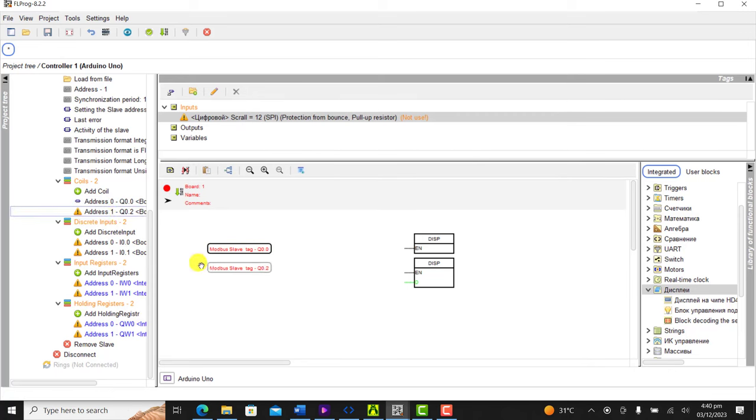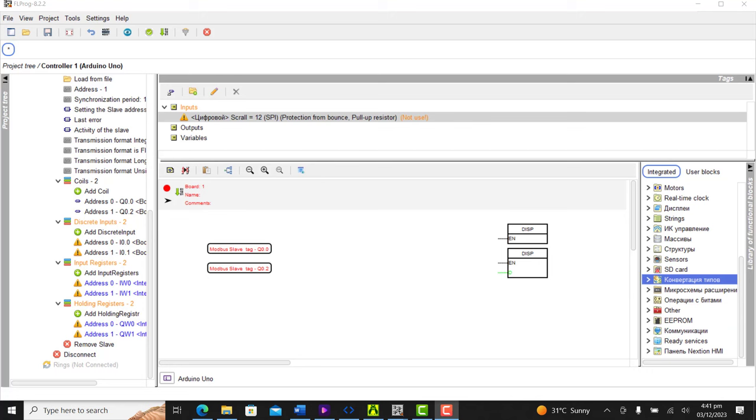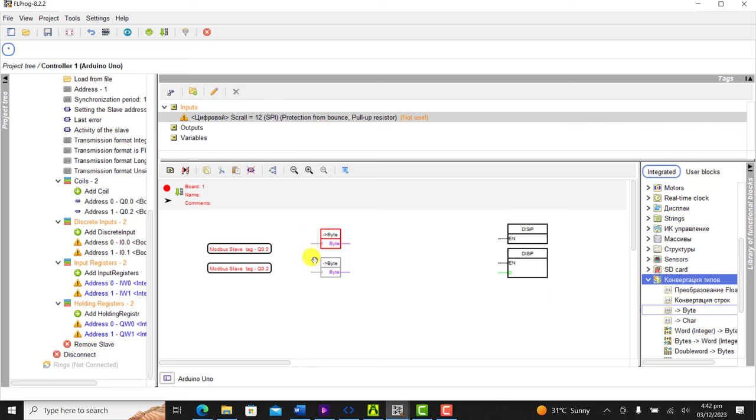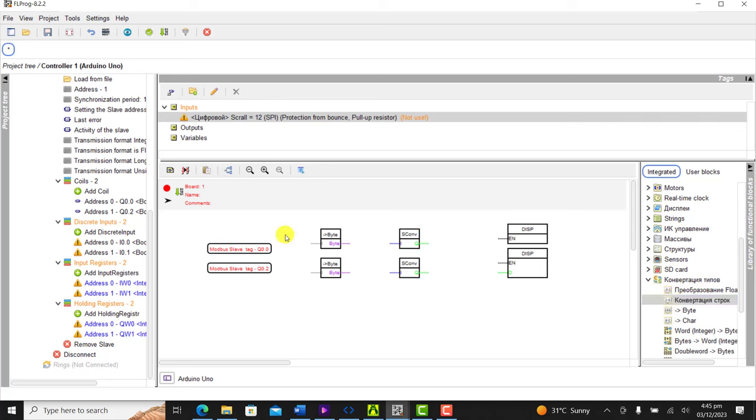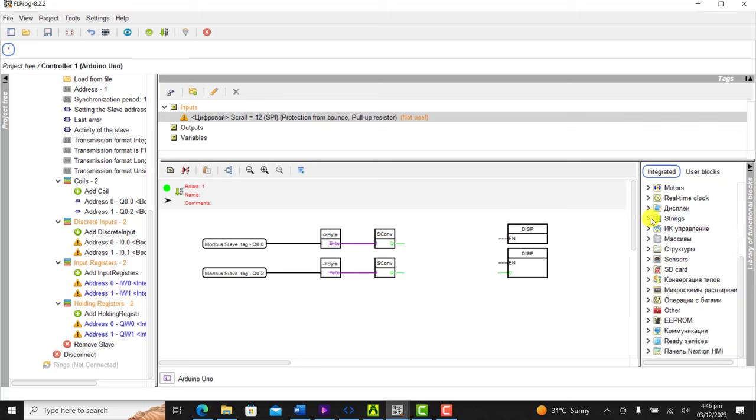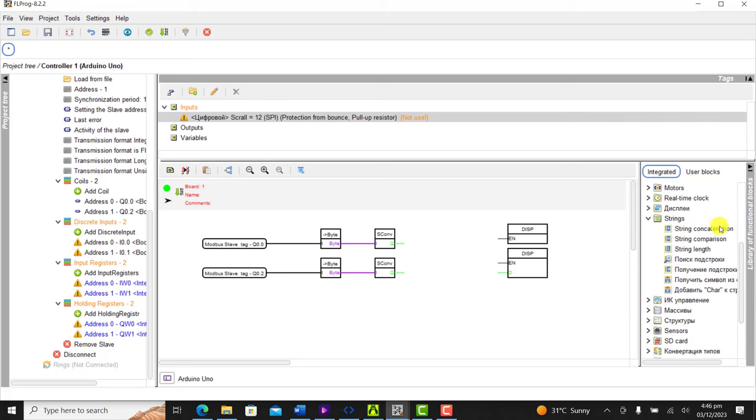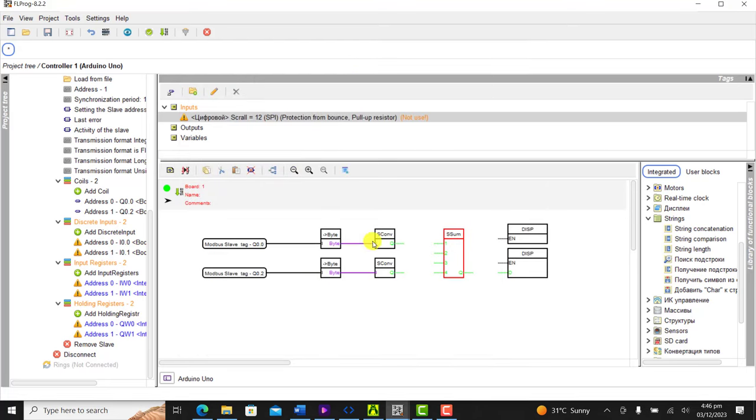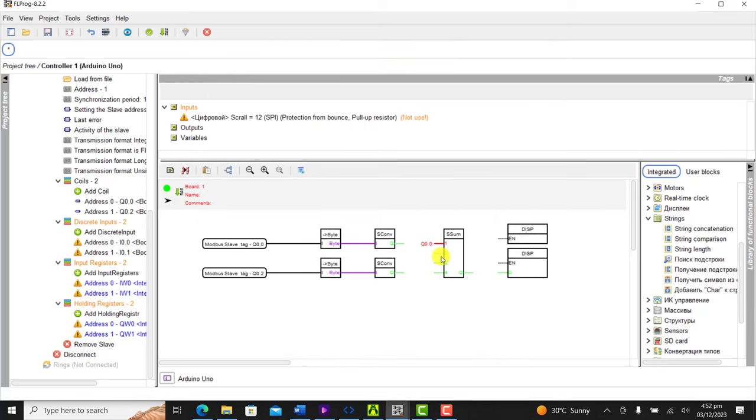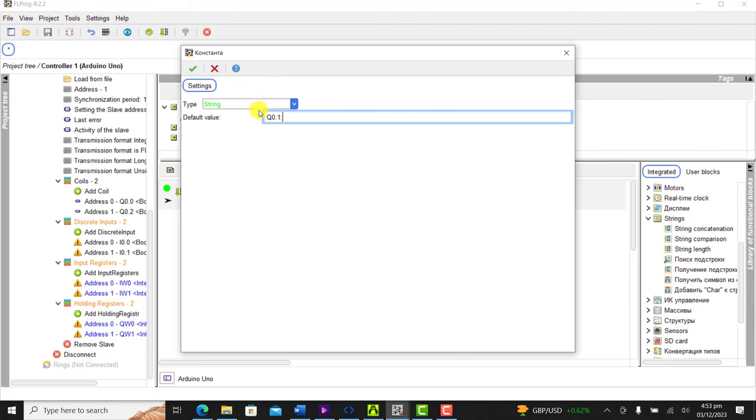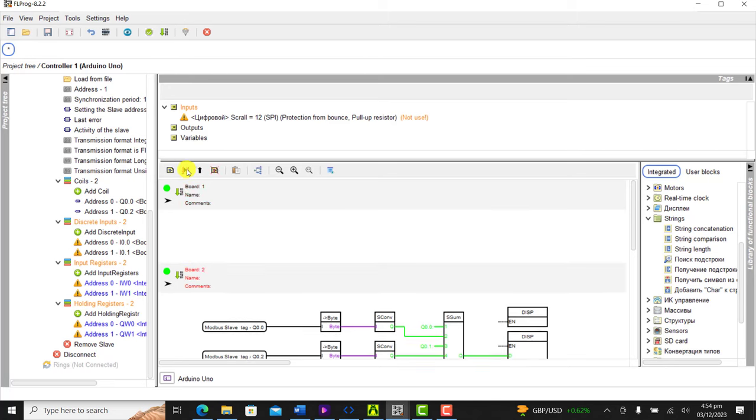We bring the coil addresses, position it correctly. Then we need a converter. We select a byte, a bit to byte converter. We drag two of them, and then we need a byte to string converter as well, two of them. We now wire them up quickly. We then need to have a concatenation block with four inputs. We specify display values or writings for this particular second row which is Q0.0 for the first value and Q0.1 for the second value. These are constant values. We wire the inputs to it and then wire it to our display.